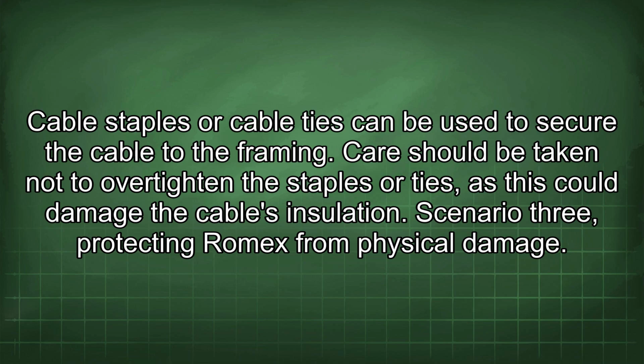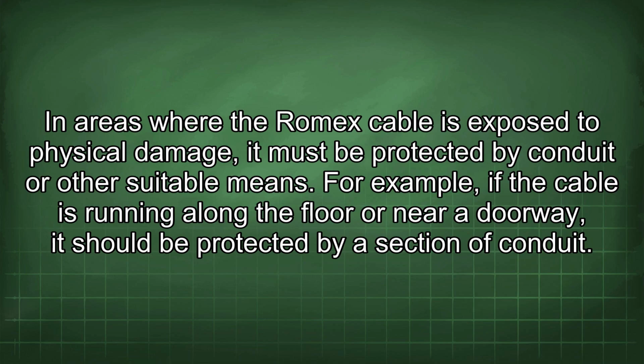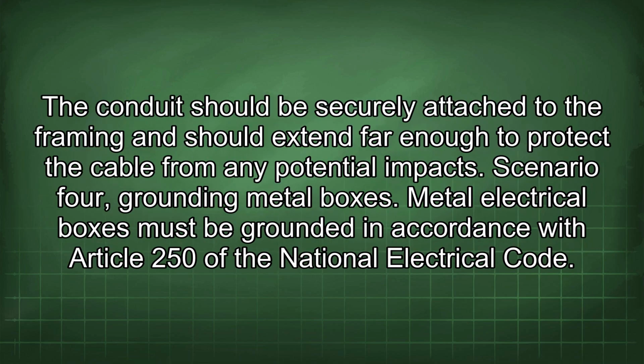Scenario 3. Protecting Romex from physical damage. In areas where the Romex cable is exposed to physical damage, it must be protected by a conduit or other suitable means. For example, if the cable is running along the floor or near a doorway, it should be protected by a section of conduit. The conduit should be securely attached to the framing and should extend far enough to protect the cable from any potential impacts. Scenario 4. Grounding metal boxes.